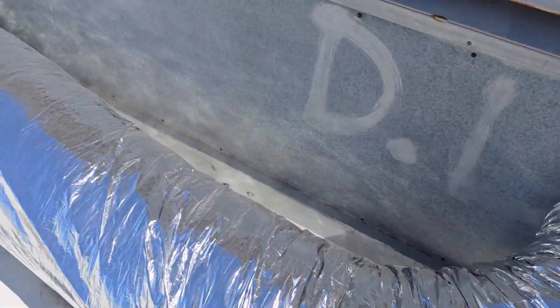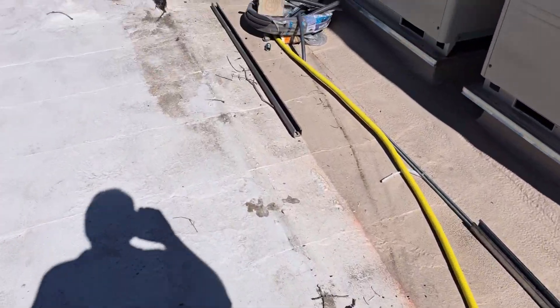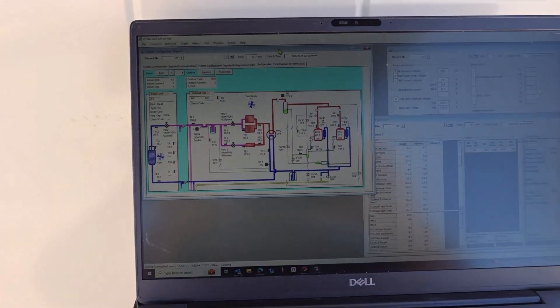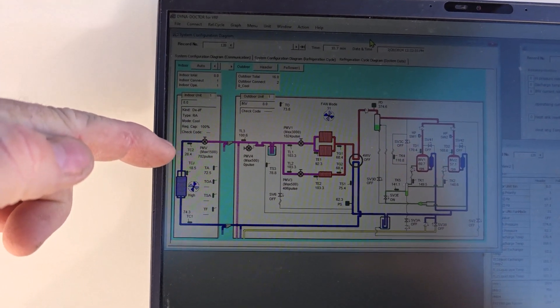This is just temporary stuff for temporary heat for the winter — they're going to remove that. It's gonna take a while. This thing's probably gonna be upset because I started it with really low airflow, so I just reset the speed on the VFD. Now it's coming up to normal — it was at like four degrees and then zero.